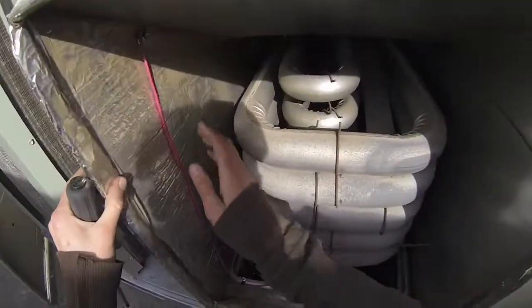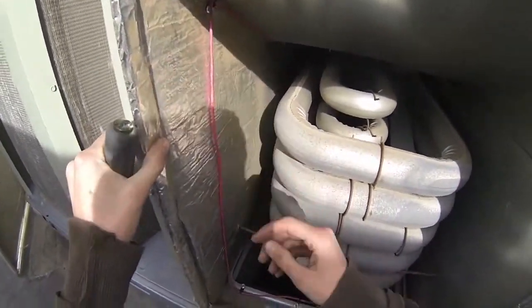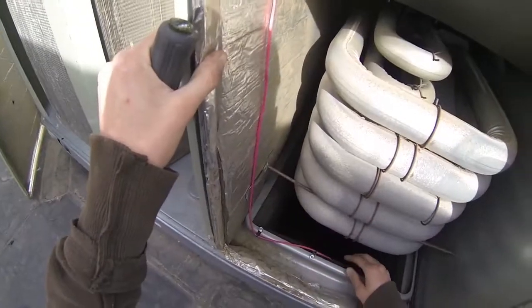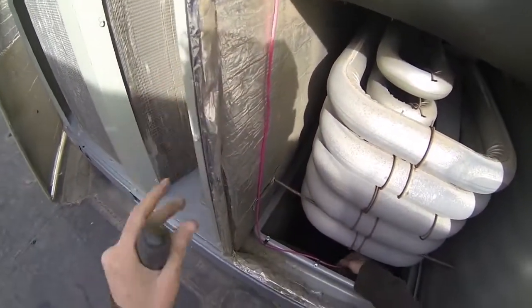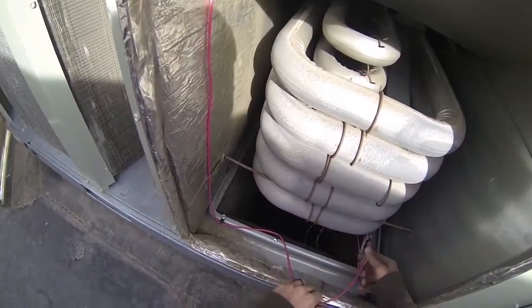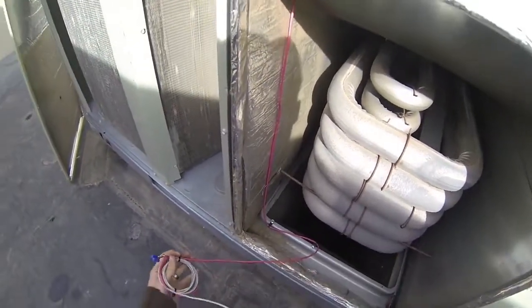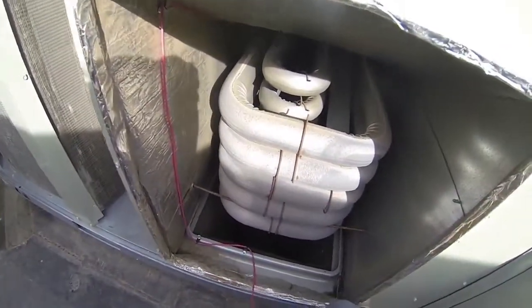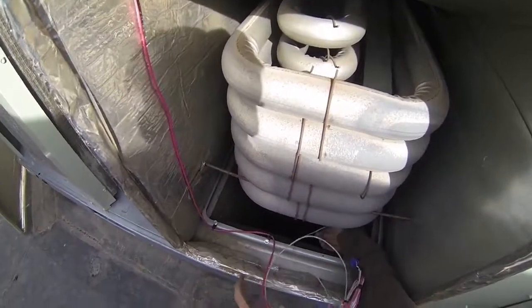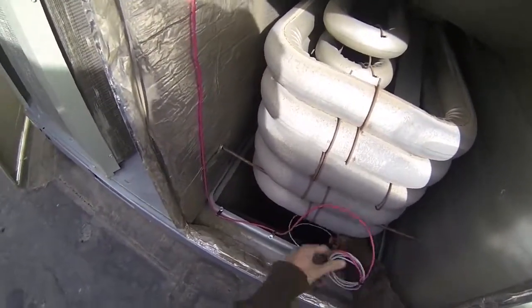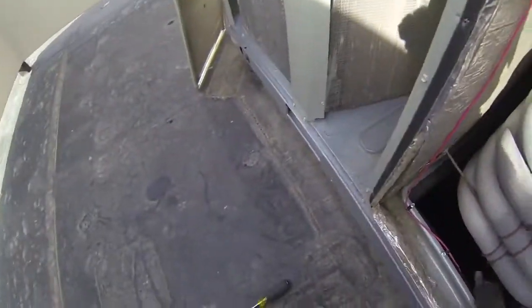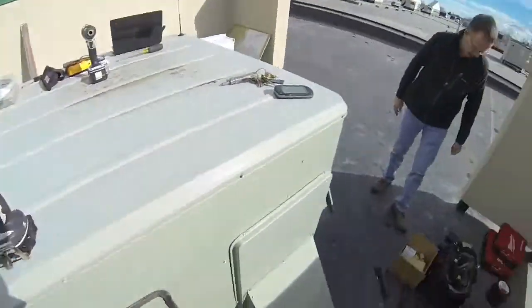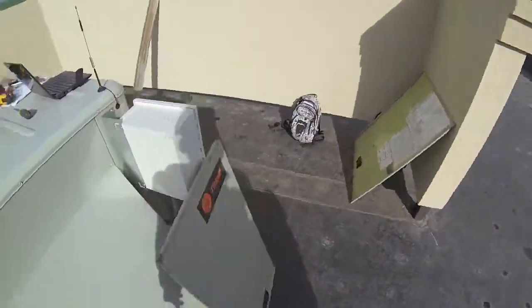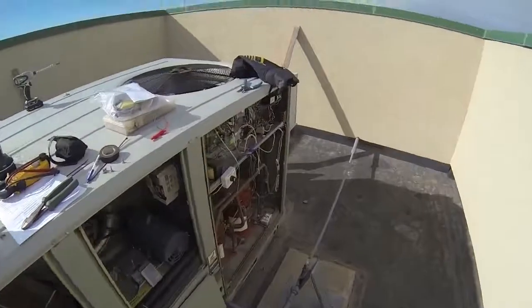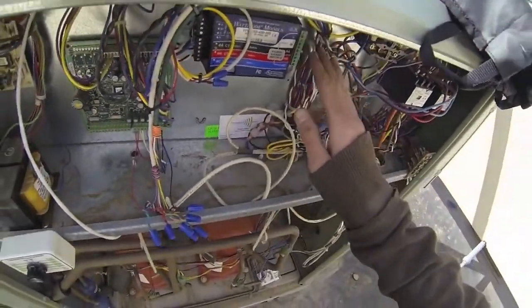We have that secured high above the heat exchanger to avoid melting from the heat of the heat exchanger. Down secured and hanging about 2 feet in to the supply, so we're in the airstream instead of picking up the heat from the heat exchanger. And the rest of our wires continue on the raceway to our electrical. They get dumped off right here.